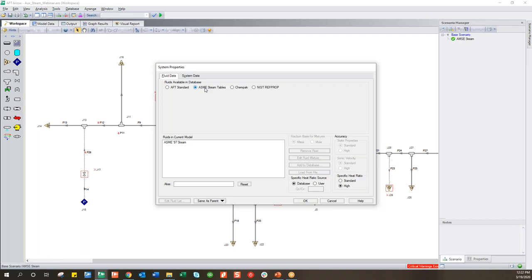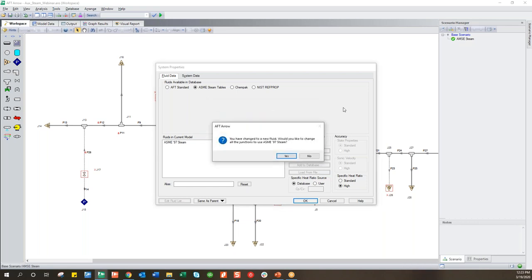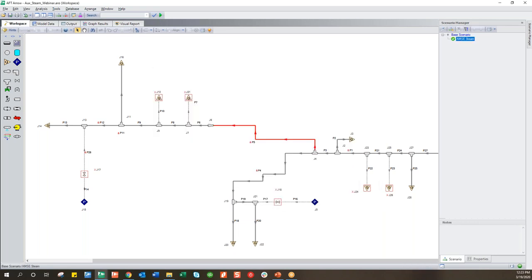Using ASME steam tables makes modeling a little more difficult because rather than having a continuous equation of state, we're interpolating between table values, so it takes a little longer for the software to solve. The good news is that with the steam tables, it will warn you of saturation conditions. It will not model two-phase flow, but it will warn you that flow has dropped below saturation and results might not be valid. What we recommend is to start off using AFT standard steam to calibrate your model — it's faster and a little more smooth as far as the solver goes.